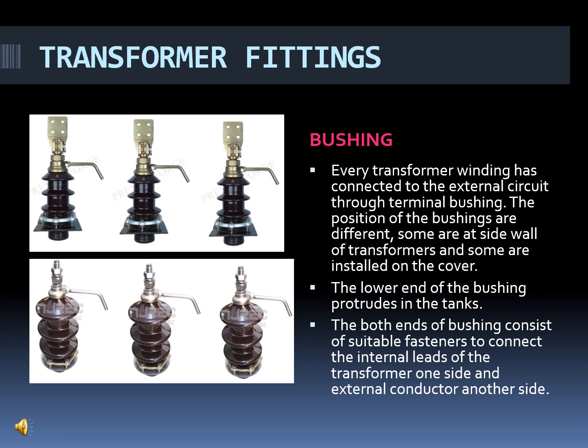Now the next fitting is the bushing. Every transformer winding is connected to the external circuit through the terminal bushing. The position of the bushings is different. In some transformers the bushing is located at the top of the tank, and in some it is inside the cover. The lower end of the bushing protrudes or dips inside the tank. Both ends of the bushing have a suitable fastener, because it is used to connect the internal leads of the transformer at one end and the external conductor, either cable or bus duct, at the other.